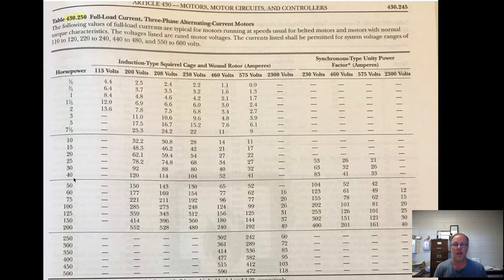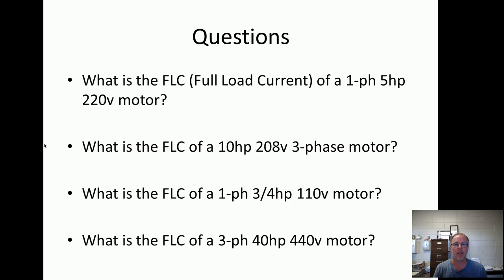We need to use Table 430-250 if it's a three-phase motor. Questions for step one: What's the full load current (FLC) of a single-phase, five-horsepower, 220-volt motor? What's the full load current of a 10-horsepower, 208 three-phase motor? What's the full load current of a single-phase, three-quarter horsepower, 110-volt motor?